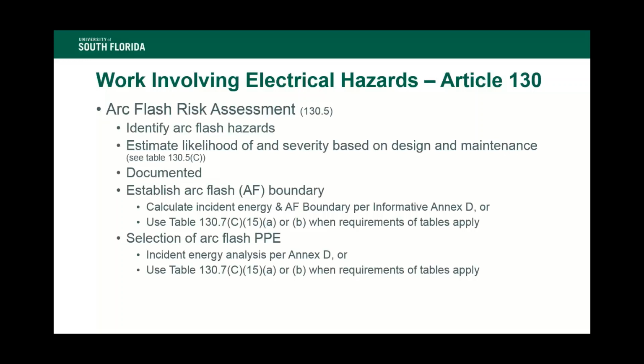And we're given two options for establishing that arc flash boundary. We can either go to Informative Annex D to calculate the incident energy and the arc flash boundary, or we can again refer to another table in Article 130, Table 130.7(C)(15)(a) or (b), when the requirements of these tables are met. And we'll see that here shortly.